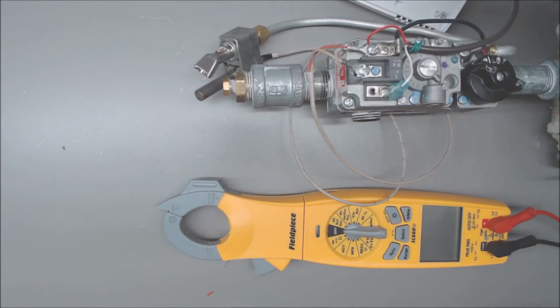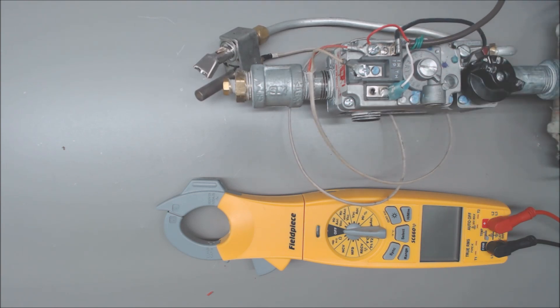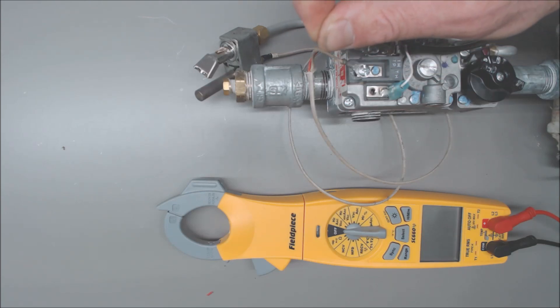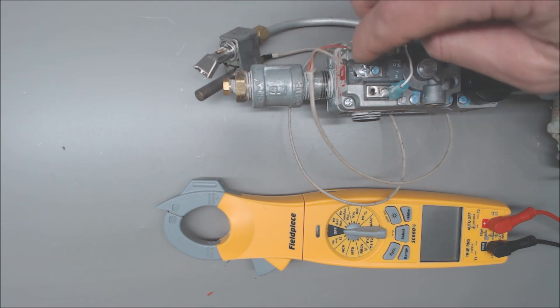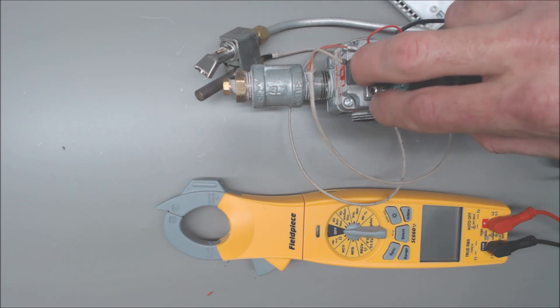The big thing about these millivolt gas valves is that you use a thermostat that is rated for 750 millivolts. If you try to use a standard thermostat, the contacts may not close completely and you might have resistance between them. You might lose your millivolts DC from when you take your reading here to where you take your reading right here.